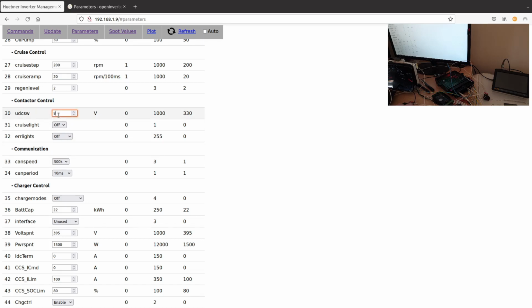Contactor control is where we set the voltage we would like the pre-charge voltage to achieve before we command the main contactor to close.